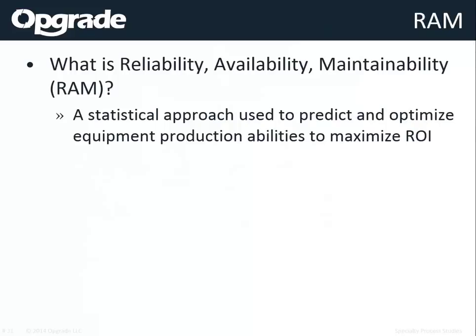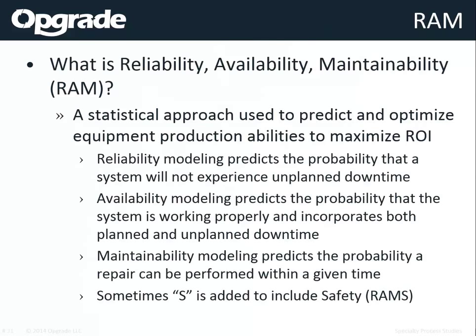Reliability is whether things are operational or not from an unplanned perspective. Availability takes that number and also adds in scheduled maintenance activities and other things that would prevent it from being operational. Maintainability is whether you can get in there and perform your maintenance activities and turnarounds in a given amount of time.